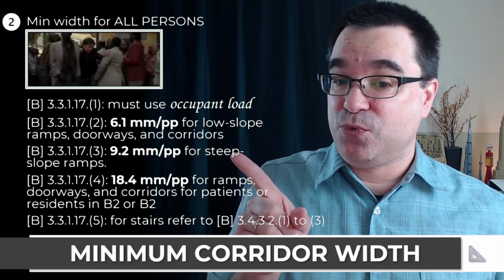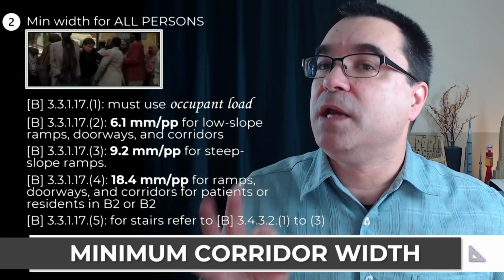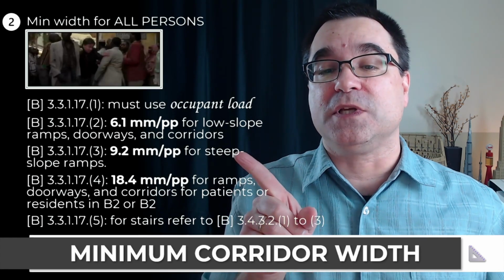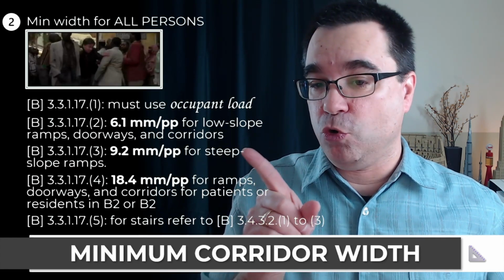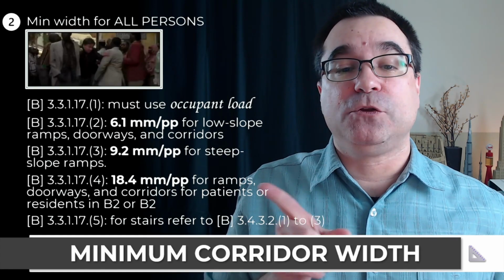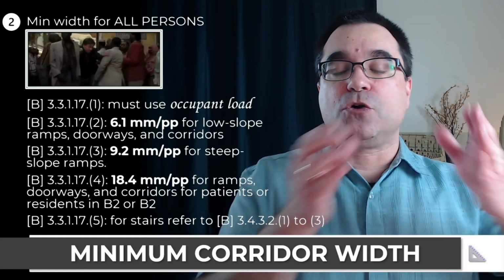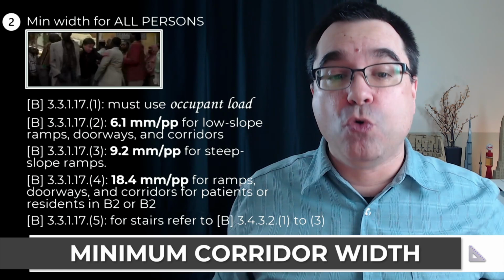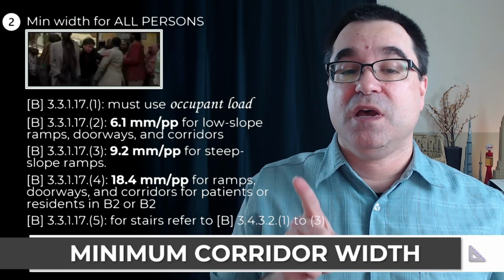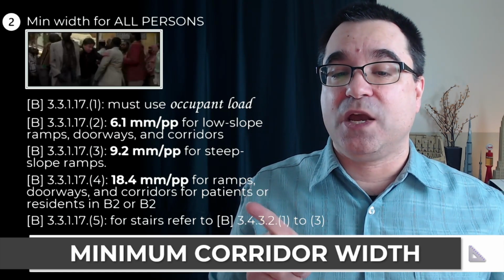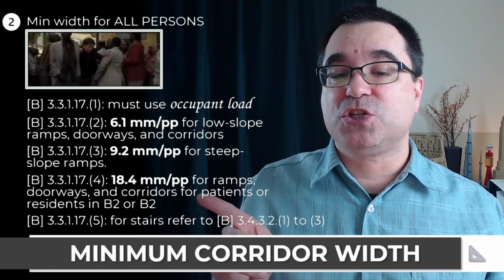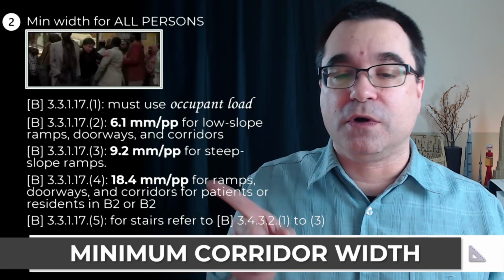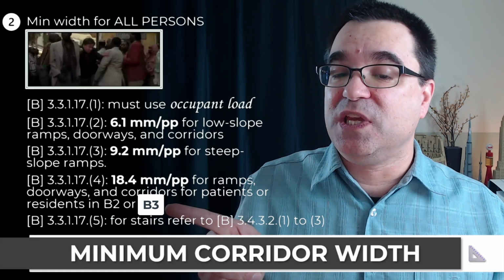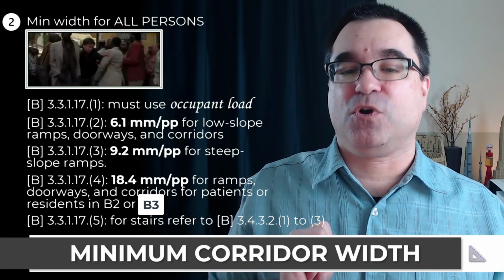Under sentence 3, that goes up to 9.2 millimeters per person for steep slope ramps. Under sentence 4, that goes up to 18.4 millimeters per person for ramps, doorways, and corridors for patients or residents in a B2, or they should say B3 occupancy.